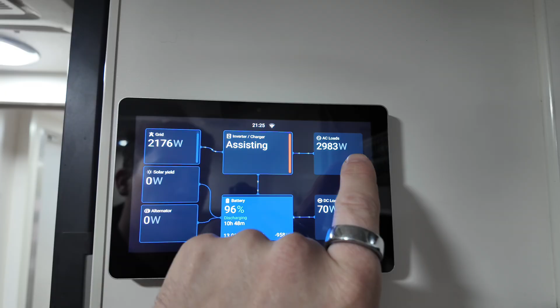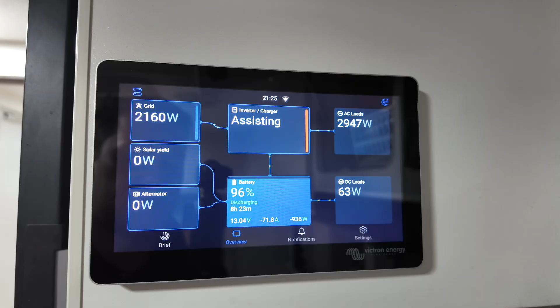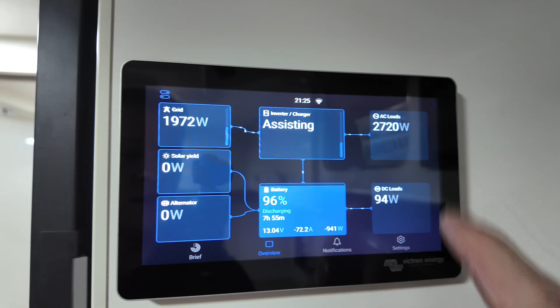We're pulling more than 10 amps off at 240 from the inverter, which we can see again if we go into here, you'll see we're pulling 12.6, 12.7 amps. There you go, the kettle's about to stop, but you can see exactly what power is coming from here going straight to here, and the batteries are assisting the inverter by pulling the power.